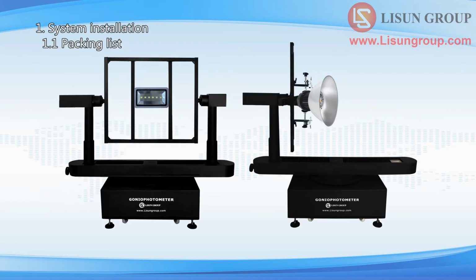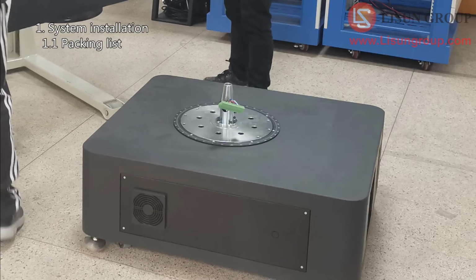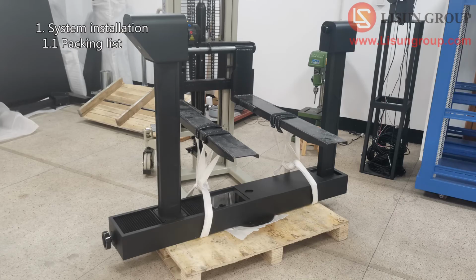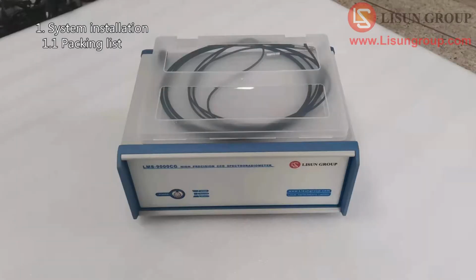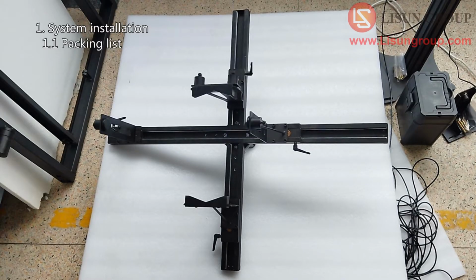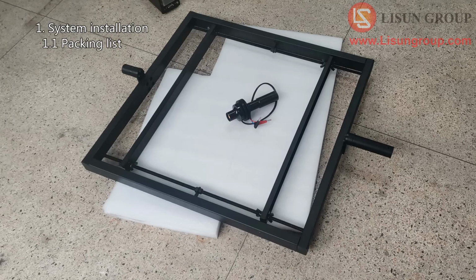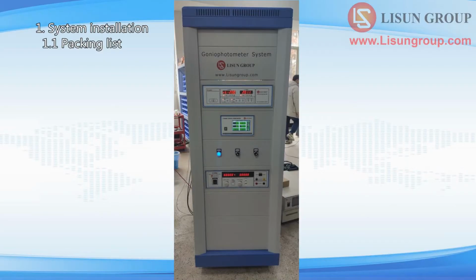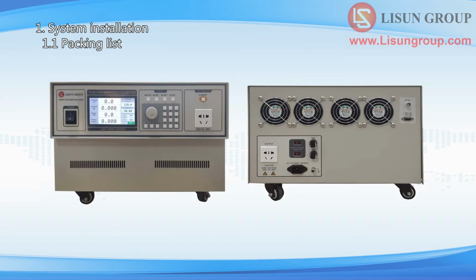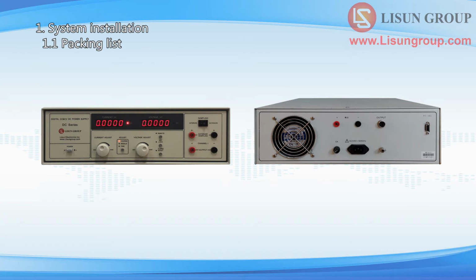Please check the packing list when you receive the shipment. There are 6 boxes for LSG-1890B or LSG-1890BCCD model. 1 box contains the base of the Goniophotometer. 1 box contains the turntable of the Goniophotometer. The spectroradiometer of the CCD model is also in the box of the Goniophotometer. 1 box contains the clamps. This is the C-gamma clamp. This is the B-beta clamp. This is the E27 holder. 1 box contains the cabinet. 1 box contains the AC power source. 1 box contains the DC power supply.